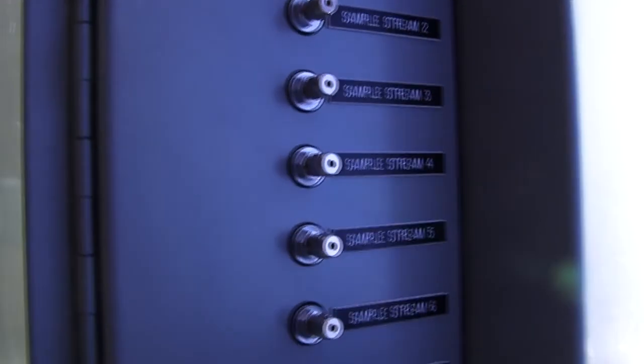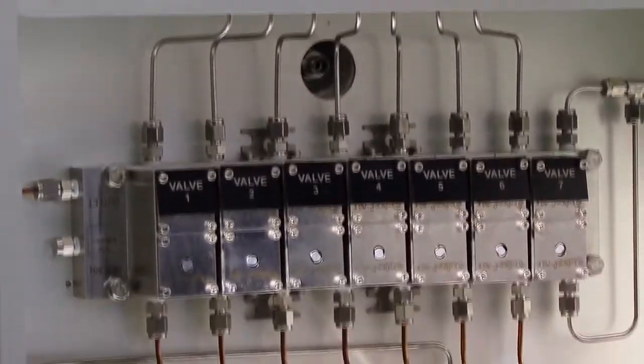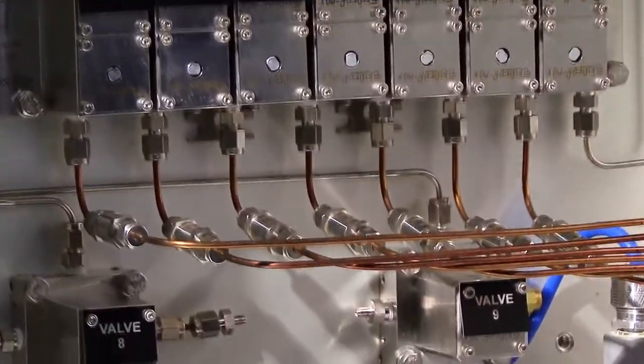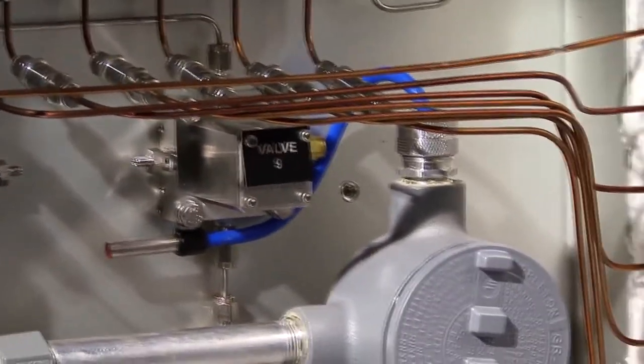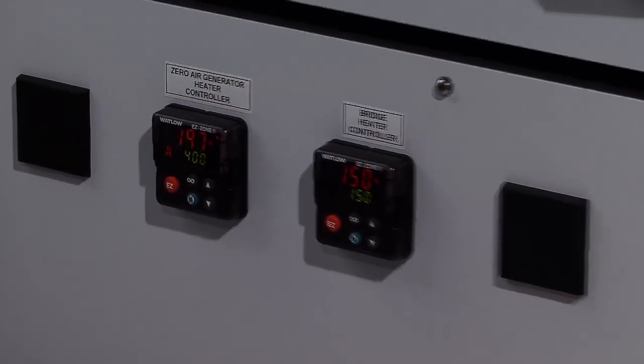On the side is mounted its sample system, a sample system that can multiplex up to 16 different sample streams. The samples can be gas, LPG, or liquid. And when required, the sample cabinet can be heated to eliminate sample corruption.